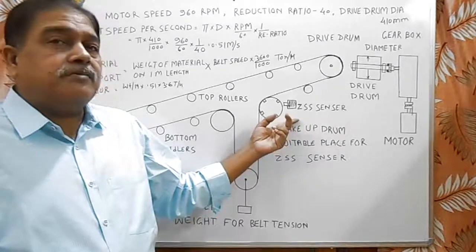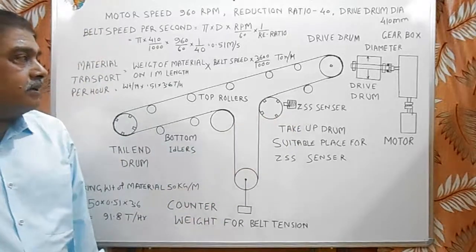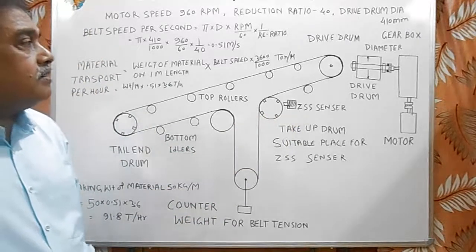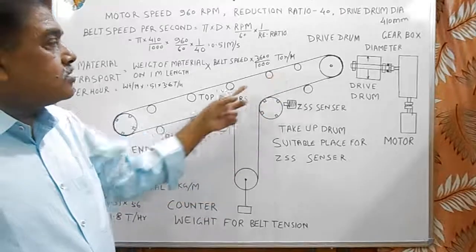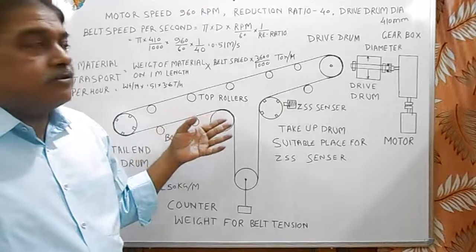So, the belt is tripped by ZSS. In addition to these, various safety devices are also used in belt conveyor. Here, number of pull cord switches are provided, so that operator can stop the belt from any pull cord switch.